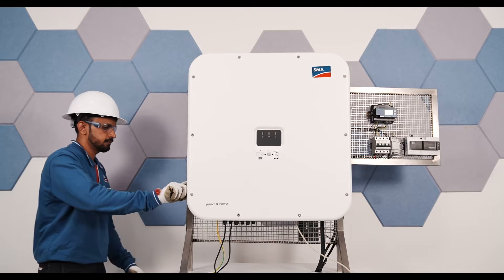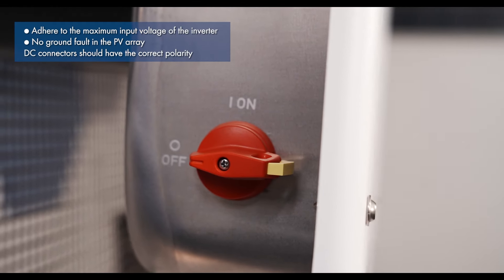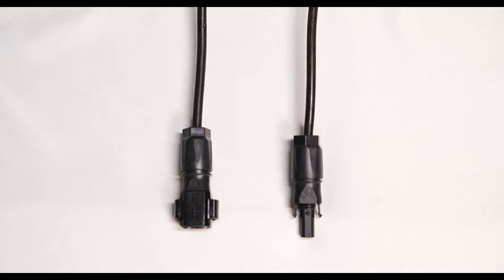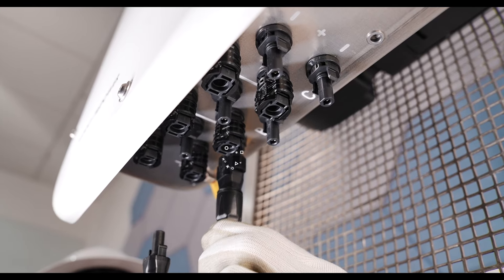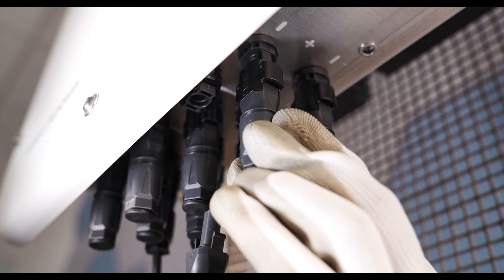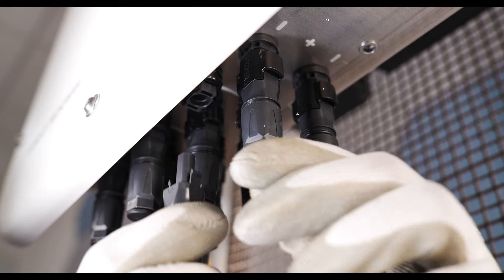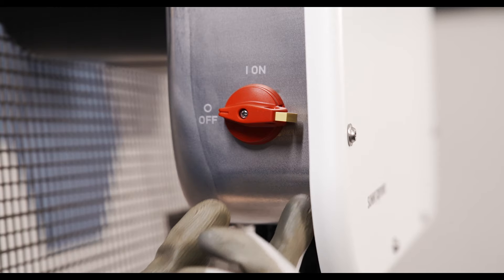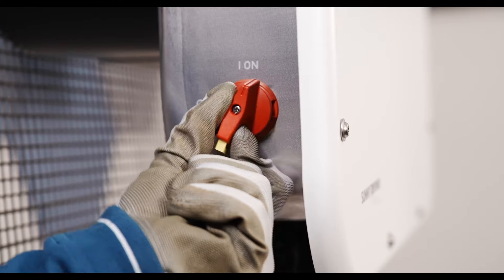Switch off the inverter's DC load break switch and measure the PV array voltage. Connect the assembled DC connectors to the inverter and ensure it is snapped properly into place. For unused DC inputs, insert the DC connectors with sealing plugs and ensure that it is securely placed. Switch on the DC load break switch and the AC circuit breaker.